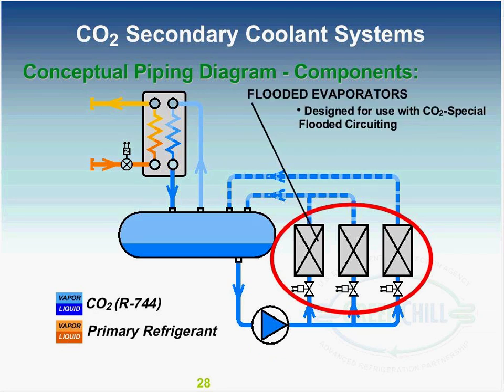Evaporators are heat exchangers that are out in the display cases or walk-in coolers or freezers. And it's important to note that this system can either be low temp or medium temp. Primarily it began use in a low temperature system. It can also be used as medium temp, and we'll talk a little bit more about that later. Evaporators are circuited special as a flooded evaporator coil. They use simple solenoid control. So when the display case needs cooling, you open the solenoid and let the cold CO2 into the display case or into that evaporator, and it boils and absorbs the heat and returns to the machine room.